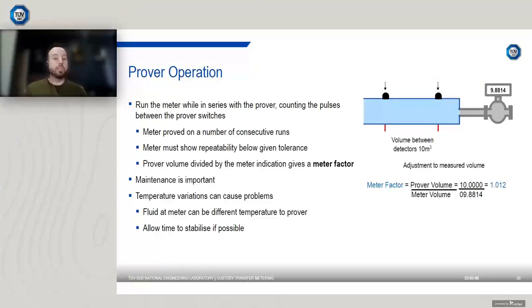So what's involved in a typical prover operation? Well, you've got the meter, or your duty meter, that you want to verify the performance of. So you run the meter in series with the prover. Typically, the prover will have a volume that's been calibrated to a low uncertainty, and the volume is held between detector switches. You're comparing the meter volume to the prover volume. If it's a pulse device, you're counting the pulses between the detector switches. Total pulses gives you an indication of the total volume from the meter. Compare that to the actual calibrated volume in the prover, and you can work out a meter factor, which you then might program into your flow computer to correct the output of your flow measurement device.